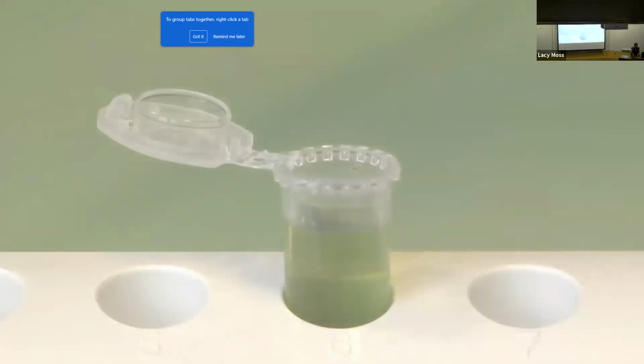Press the control button down to the first stop and immerse the tip into the liquid. Once the aspiration angle and immersion depth have been checked, slowly release the control button. Press the control button down to the first stop again and aspirate once more.